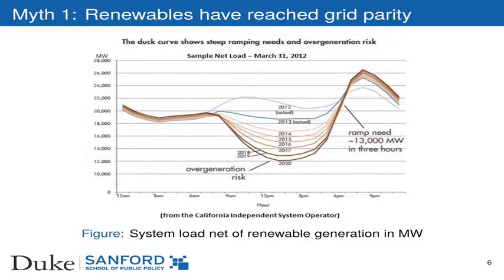So this figure is showing the net generating capacity. It's a model out of California showing the net load on the system in California, net of the renewable generation over the course of a day. And what we see is that the net generation, so that is the generation that's required net of renewables, by the dispatchable generators, is quite low during the early to mid afternoon. But the peak demand occurs later in the day when the sun starts to set. And so the renewables start providing less generation, which requires the dispatchable generators to begin to ramp up and produce more electricity. This is called the ramping cost.